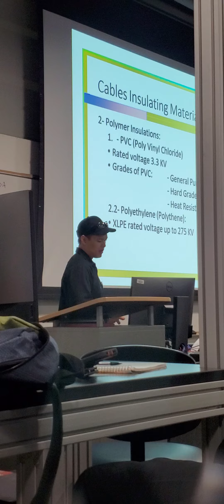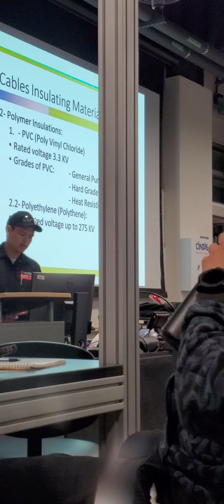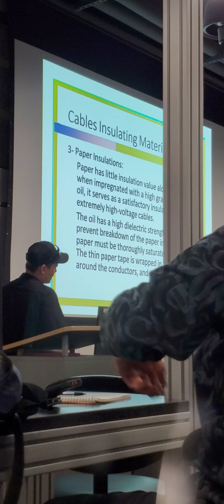And polyethylene, XLPE, rated voltage up to 275 kV. Paper has little insulation value alone. However, when impregnated with a high grade of mineral oil, it serves as satisfactory insulation for extremely high voltage cables. The oil has a high dielectric strength and tends to prevent breakdown of the paper insulation. Paper must be thoroughly saturated with the oil. Thin paper tape is wrapped in many layers around the conductors and then soaked with oil.